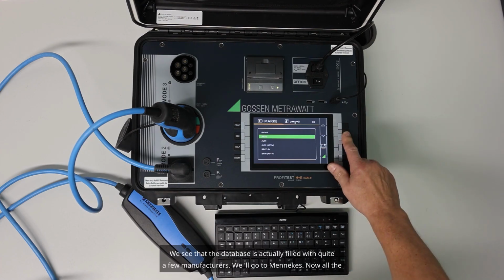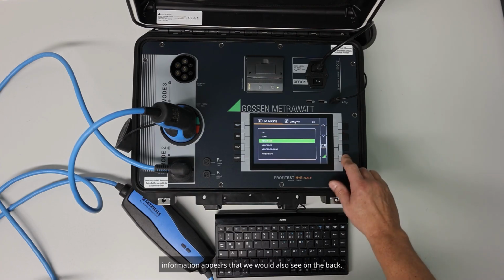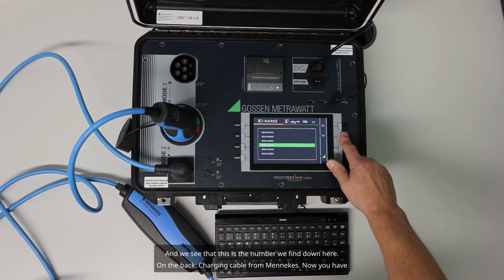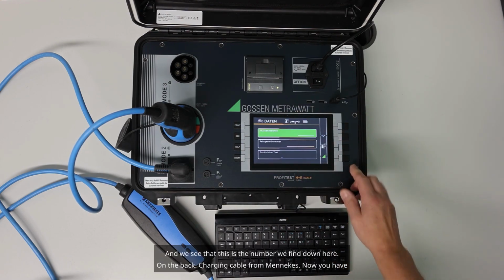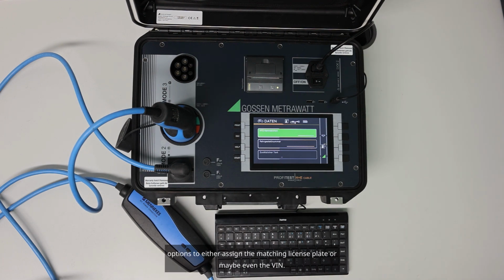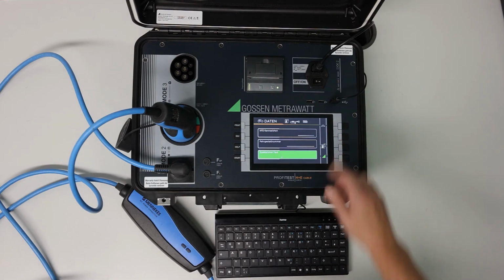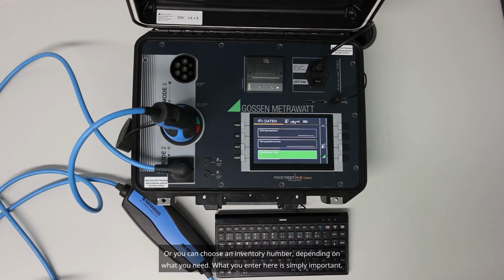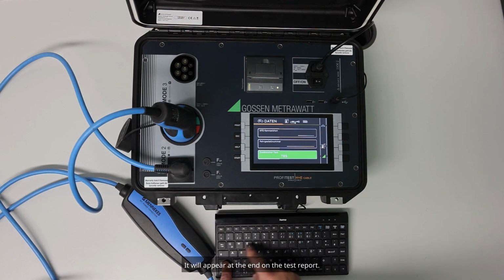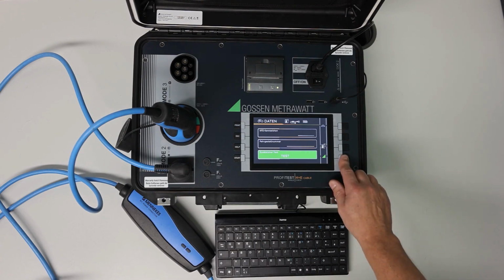We see that the database is actually filled with quite a few manufacturers. We'll go to Mennekes. Now all the information appears that we would also see on the back. And we see that this is the number we find down here on the back. Charging cable from Mennekes. Now you have options to either assign the matching license plate or maybe even the VIN. Or you can choose an inventory number depending on what you need. What you enter here is simply important. It will appear at the end on the test report.